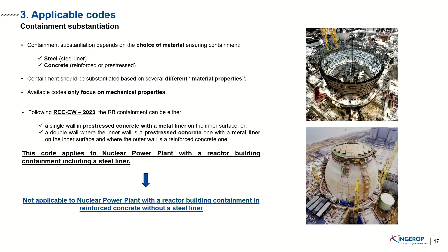So continuing with this, for reinforced concrete containments without a liner, the applicable codes only provide criteria for substantiating containment based on crack control and stress limitation, but they never address an estimation of the actual potential leak rate in a concrete structure subjected to an important value of temperature and pressure. This implies that applicable codes today do not furnish any substantiation for the leak rate assessment criteria.